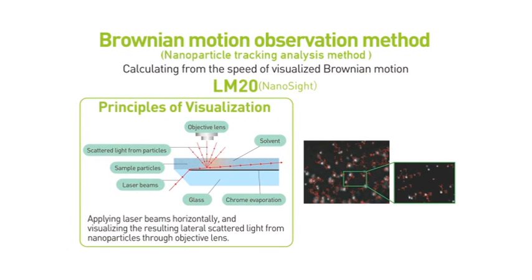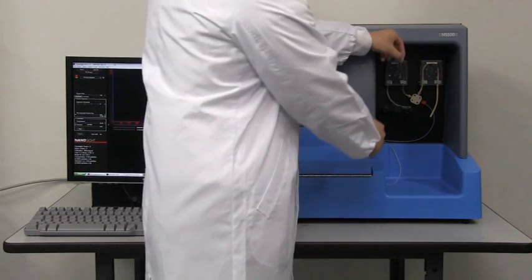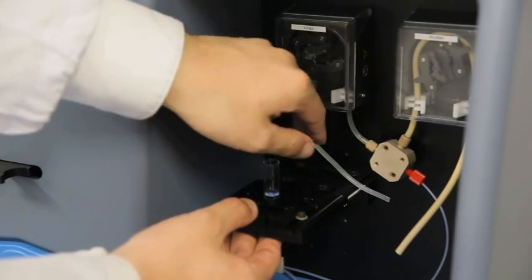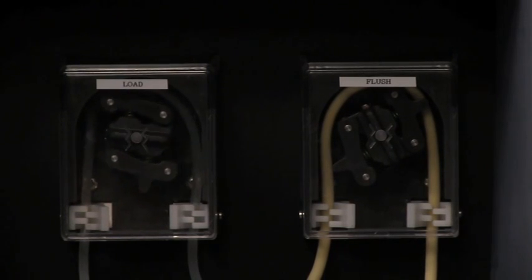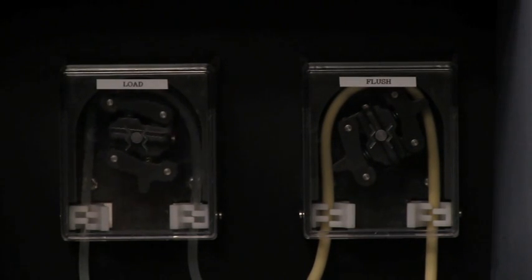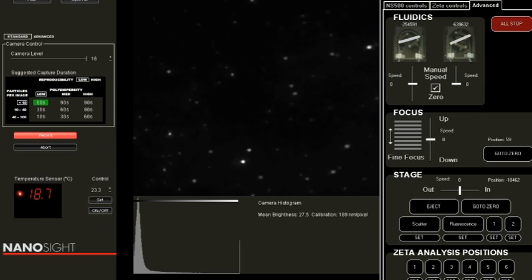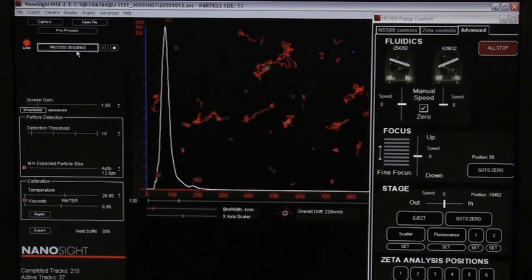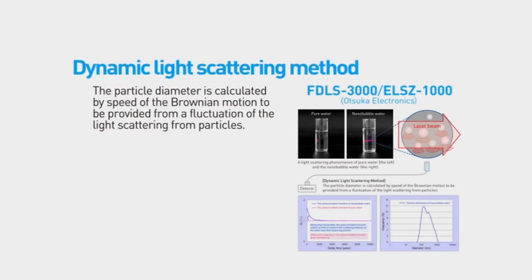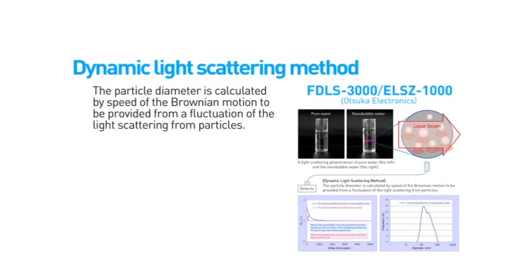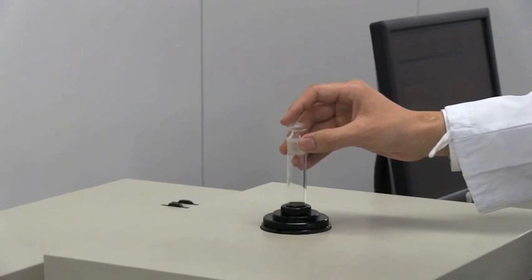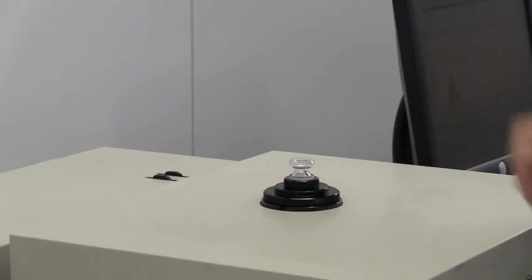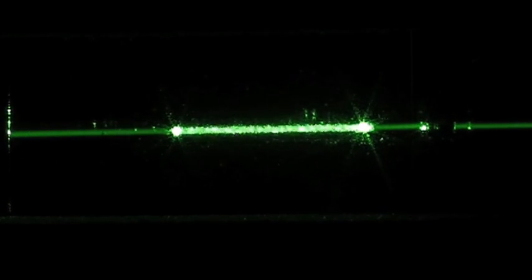These methods include a Brownian motion observation method that tracks the bubbles' Brownian motion, and a dynamic light scattering method that irradiates the ultra-fine bubbles dispersed within a liquid with a laser, monitors the fluctuation of the light scattered due to the bubbles' Brownian motion, and then calculates the bubble size distribution using a Stokes-Einstein equation.